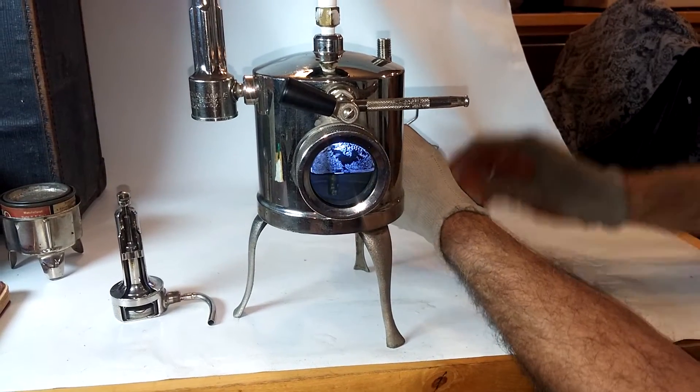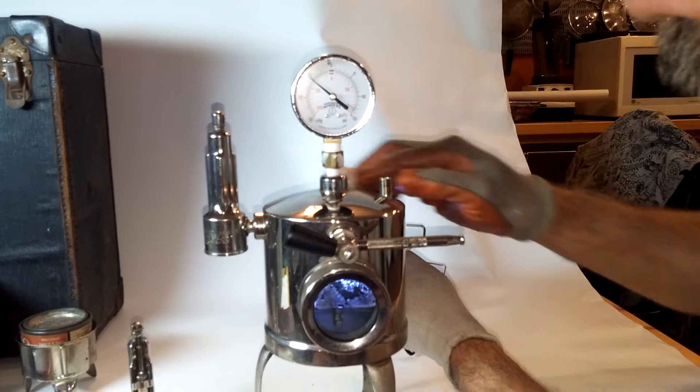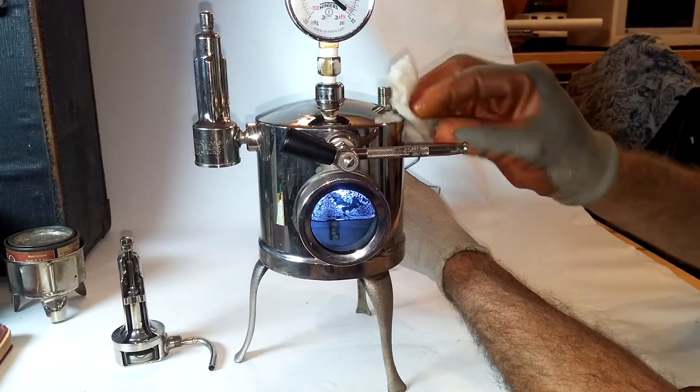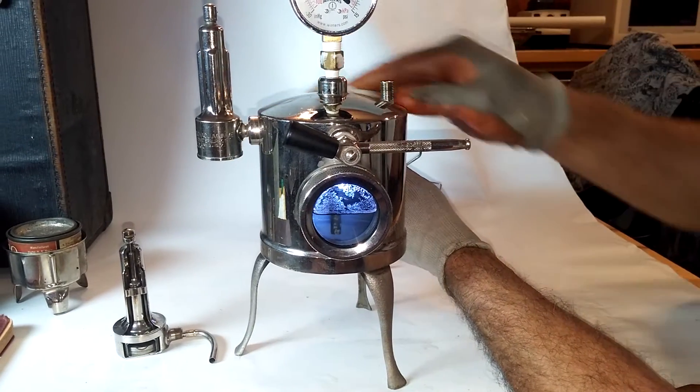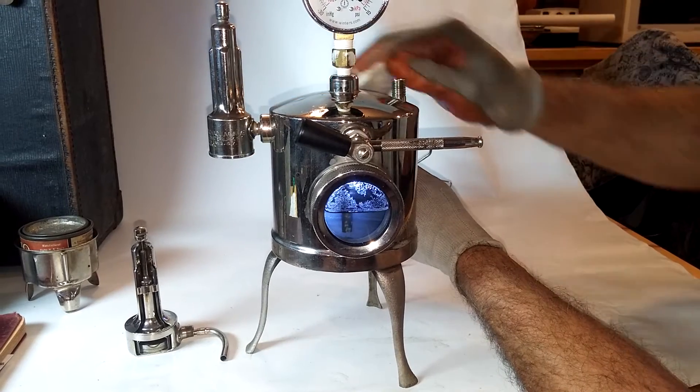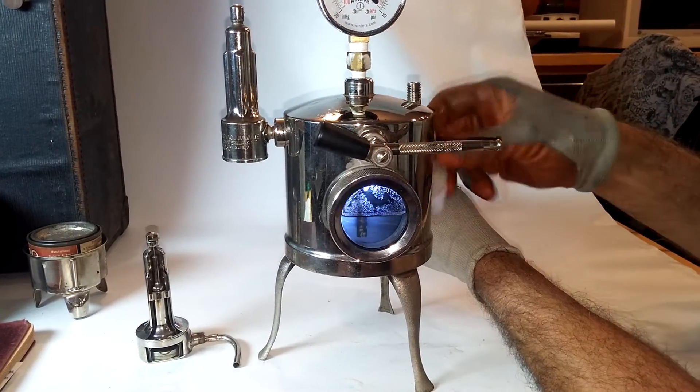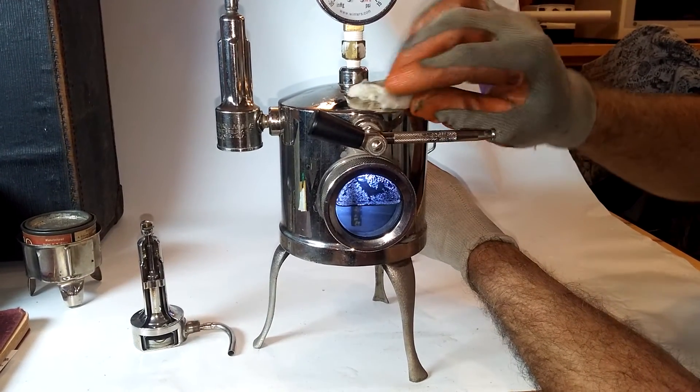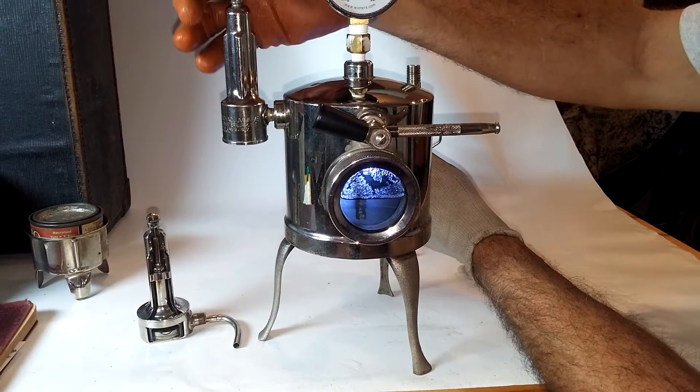You see we're down almost to ten inches of mercury, and the water is still boiling. So this was used, the Hoffman slogan was the watchman of the coal pile. This allowed, when the coal fire burned down, to be able to still continue to heat the building with all these vacuum checks.